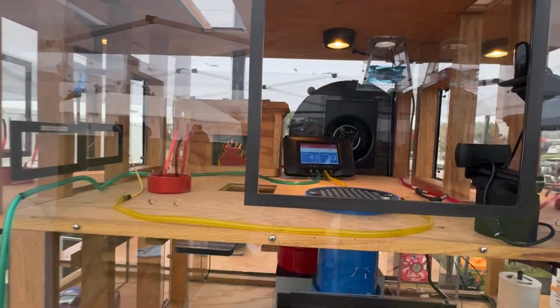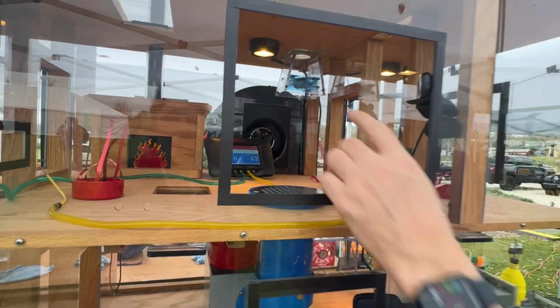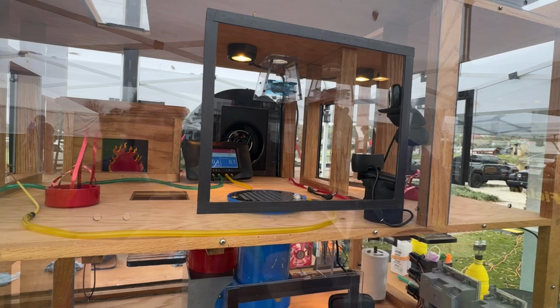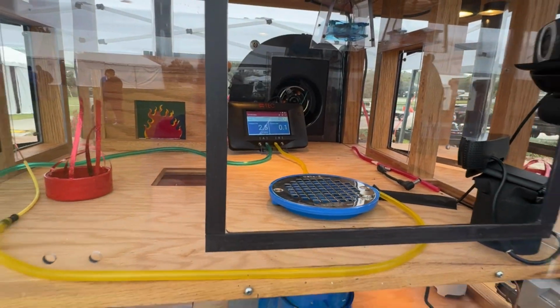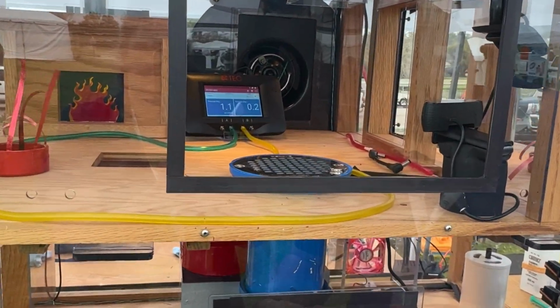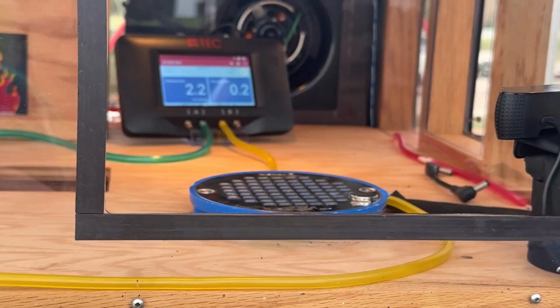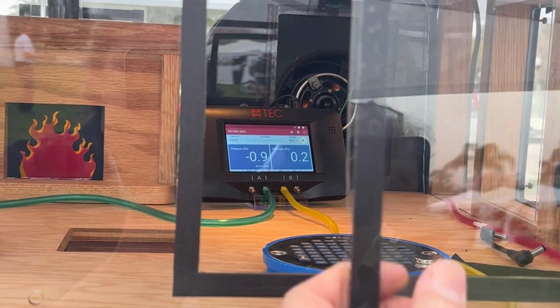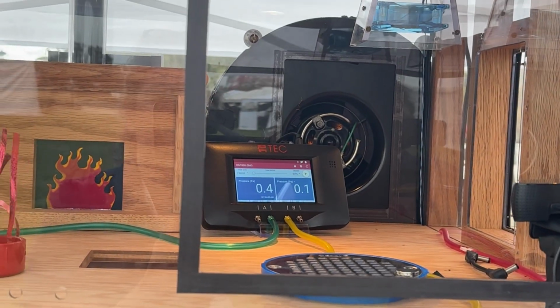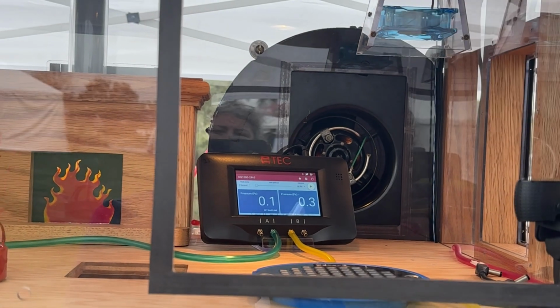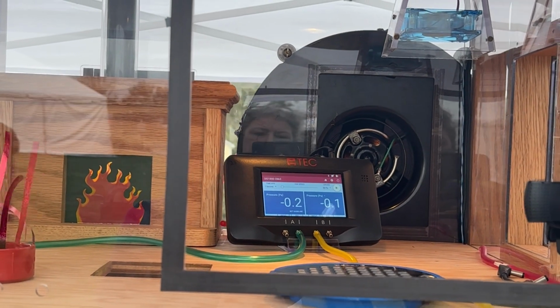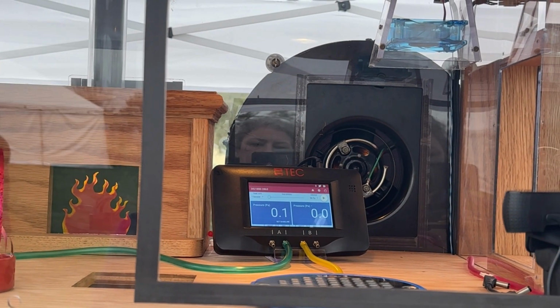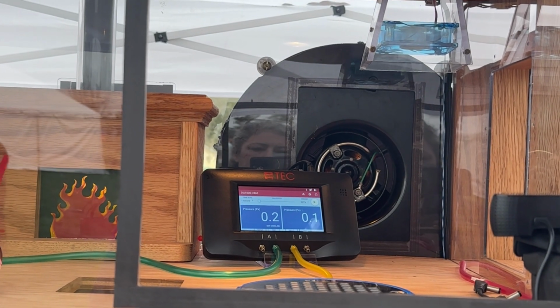I see this device here, it has some numbers on it. We're going to look at the number on the left where that green hose is, and that green hose actually goes outdoors. Right now I've got the window off the house, and I'm going to put the leak back on that we had, just to show you what it should look like. So basically we're measuring the pressure difference between inside the home and outdoors.